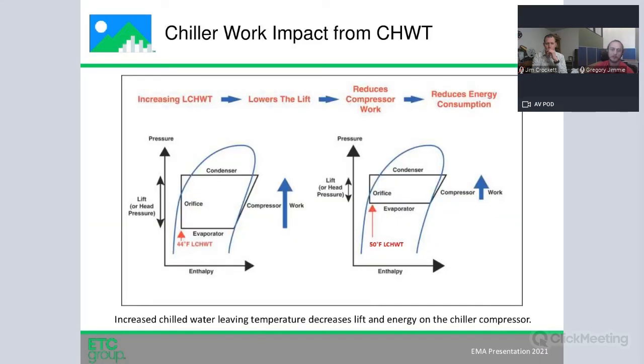So we'll start off with the first most common solution, getting away with warm chilled water. That's something that isn't new to anybody familiar with chiller operations on how to save some energy. But what may be new is the way in which you want to go about doing it. How do you know when you can reset to warmer water, or how warm can you go? We will look at a strategy on how to automate that process and make your system respond. I like to think of it as ebb and flow, or responding to the demand of your systems and the capacity required to satisfy your chilling demands.